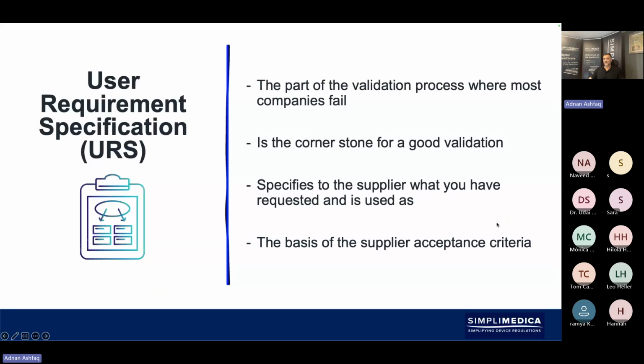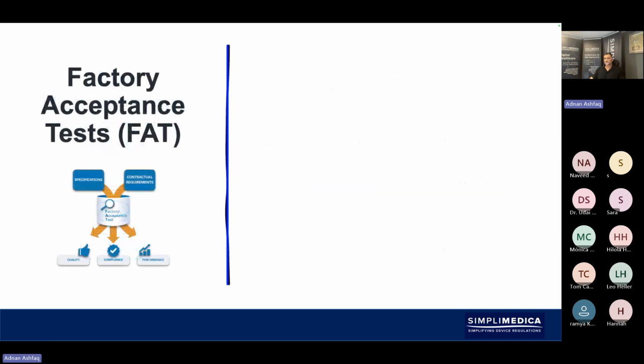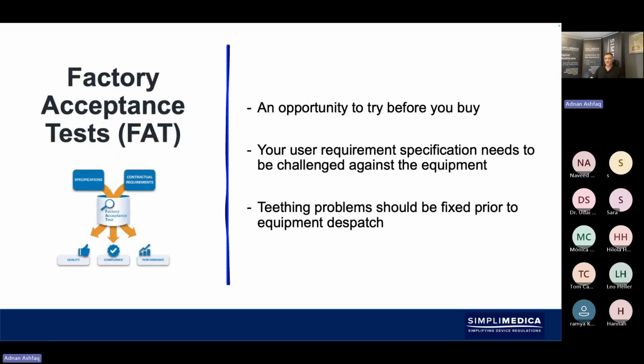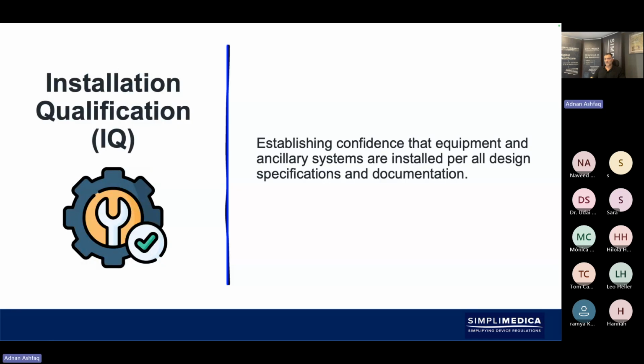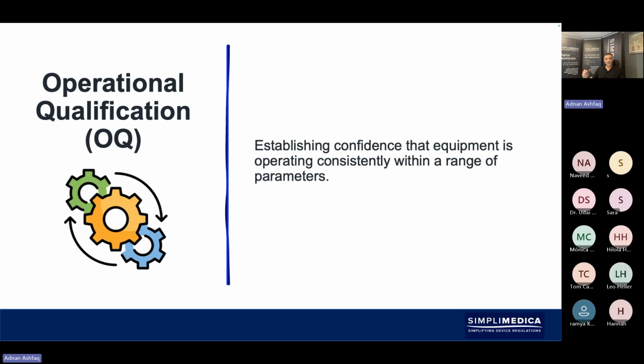So again, user requirement specifications, we do this because it's a cornerstone. It specifies to the supplier what you have. It's the basis of acceptance criteria. The factory acceptance, we do that because it's an opportunity to try before you buy it. It's also your fail-safe. It allows you to remove any teething problems. The IQ we look at to ensure that we have established confidence within equipment and ancillary systems that are installed to the design specifications and documentation. We look at OQ because we want to make sure that we've got the operating windows and we have the confidence in the parameters, where there's always drift in manufacture.